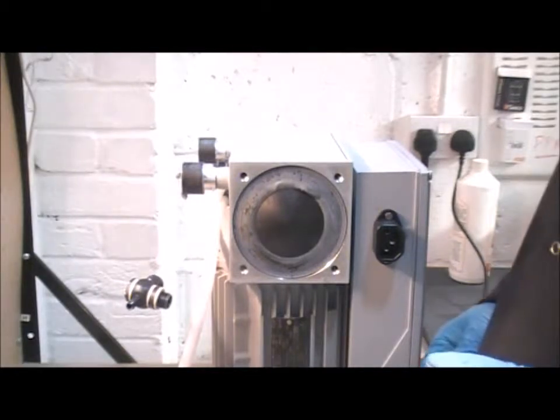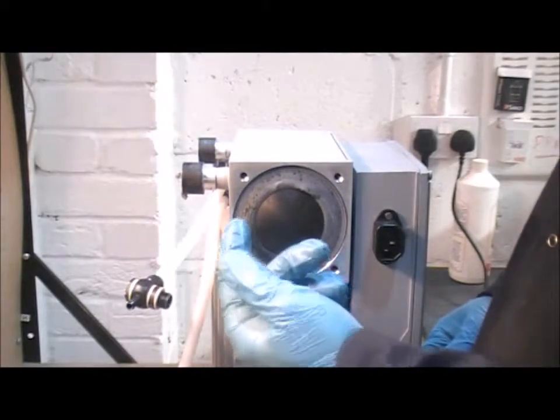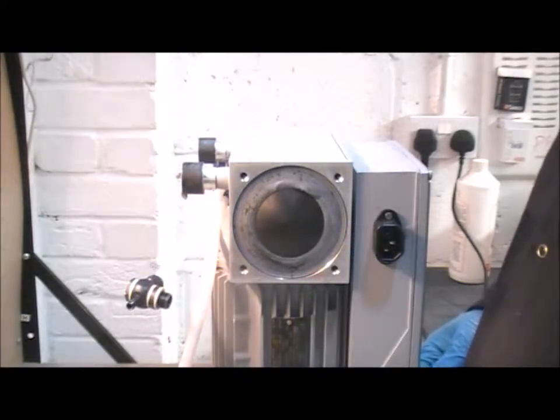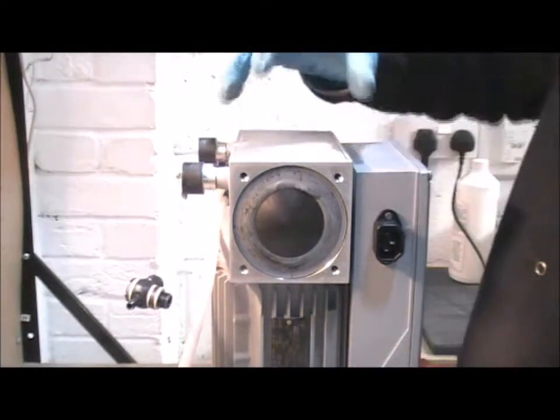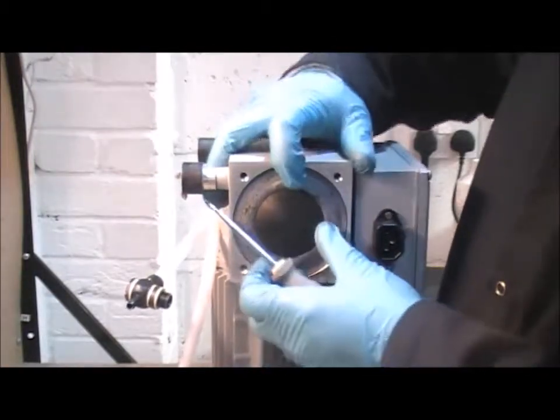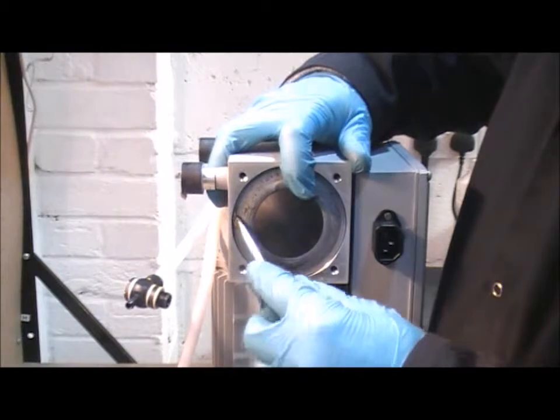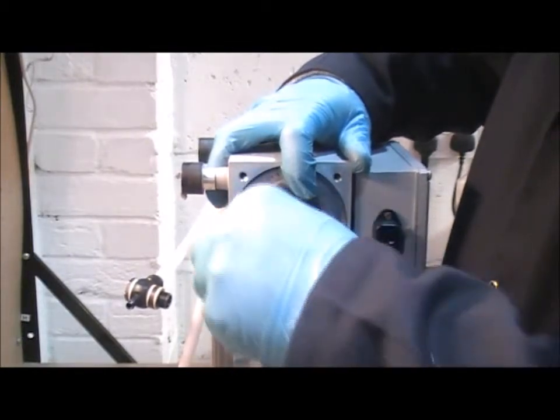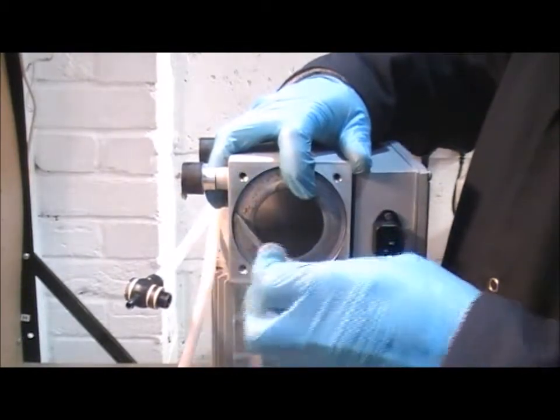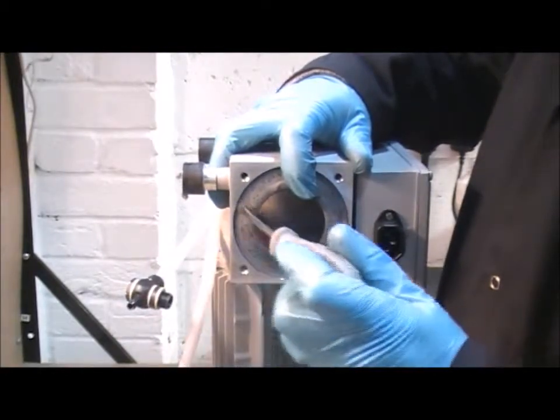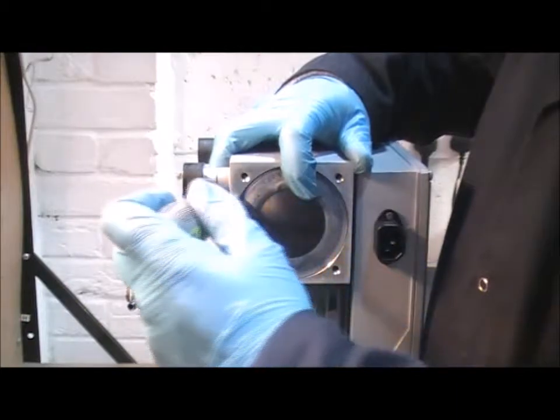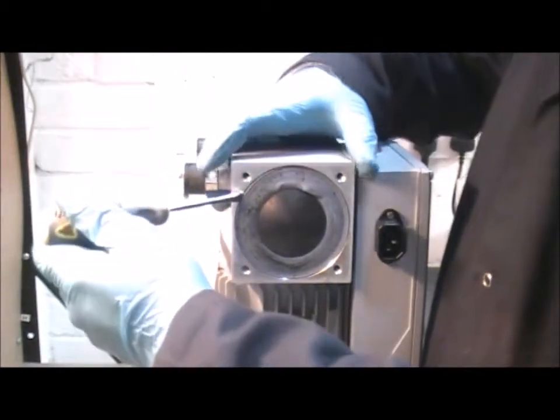What I need to do next is actually release the diaphragm from the mounting where it is. To do this I'm going to use a flat blade screwdriver. This can be a little bit tricky, just be patient with it. Get the blade of the screwdriver down behind the edge of the diaphragm and you should be able to just pop it up like that.